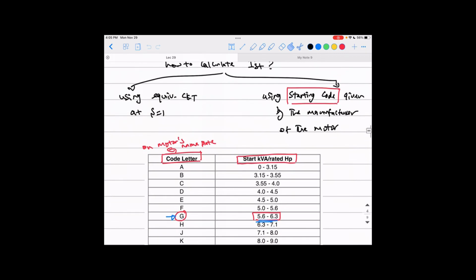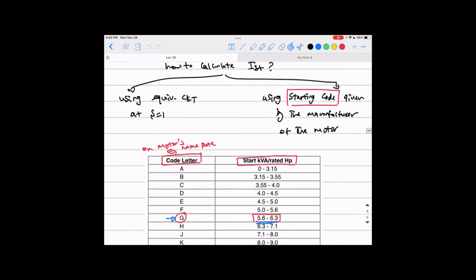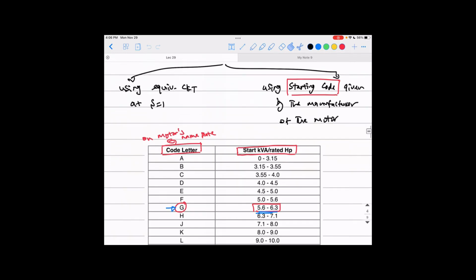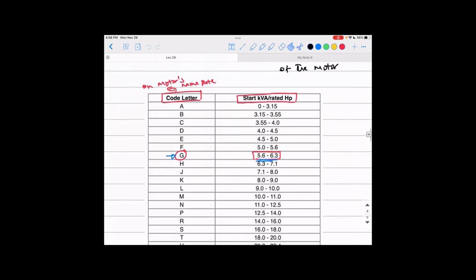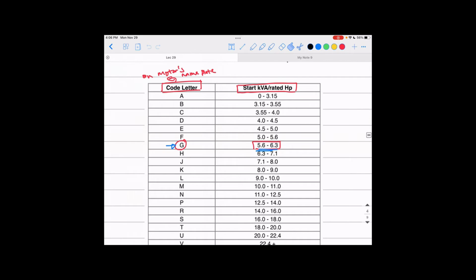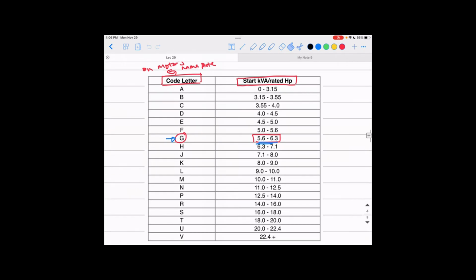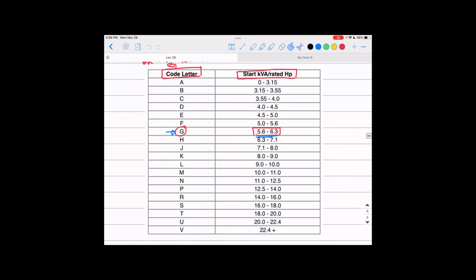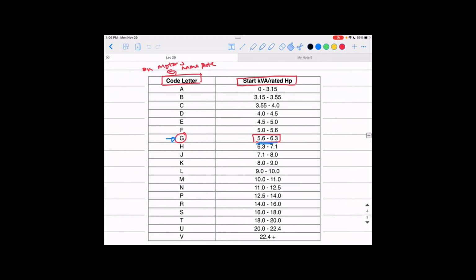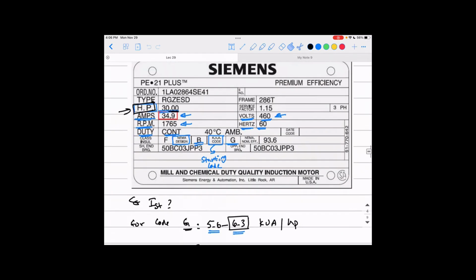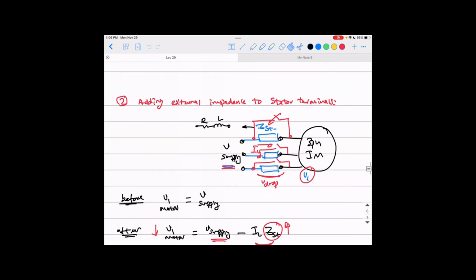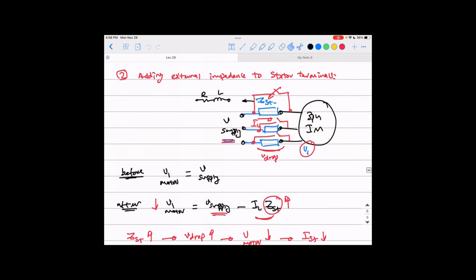Like we said, we can find the starting current that the motor draws without any means of reduction for this starting current, meaning a starting method. We can simply use the equivalent circuit to find this current, putting the slip at 1 because that's the starting slip, if you have the equivalent circuit parameters. But if you don't, the manufacturer provides you what we call the starting code. You can find it on the nameplate of the motor, which is attached to the outer case of the motor. You will find a code over there that you can use with this table to find a range for the expected starting kilovolt-ampere per rated horsepower, and then you can calculate the starting current from it, like we did in the last lecture. And if you want to reduce the starting current, you're going to go with one of these methods.